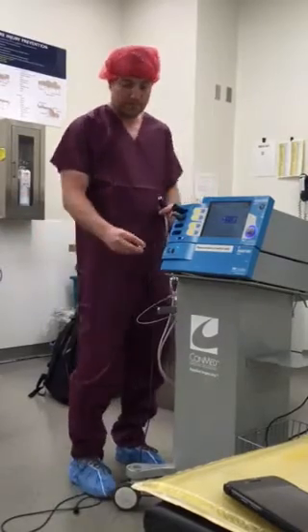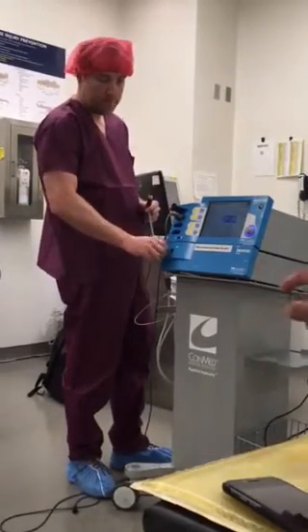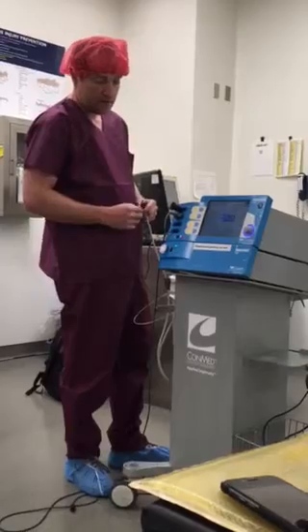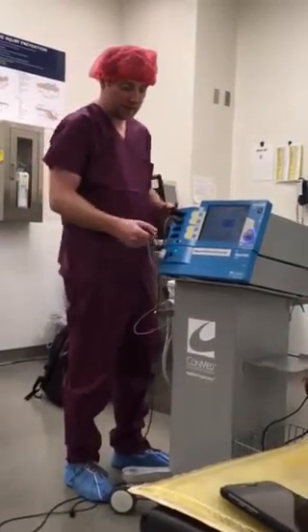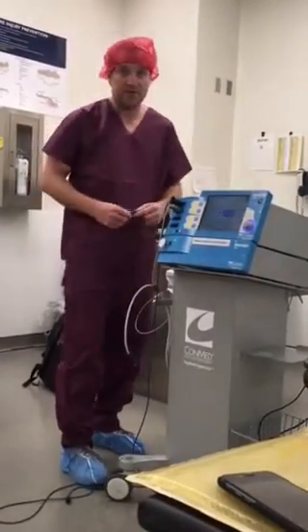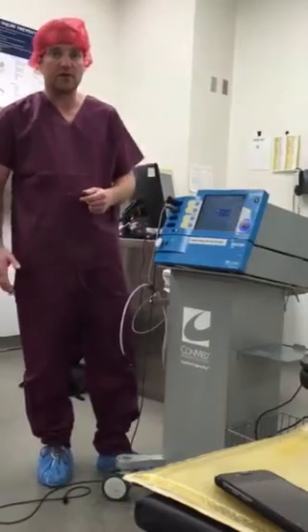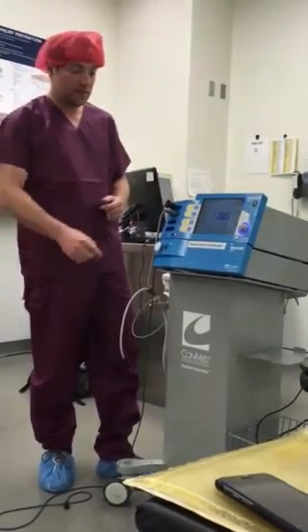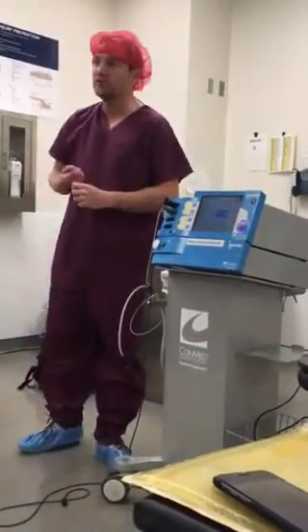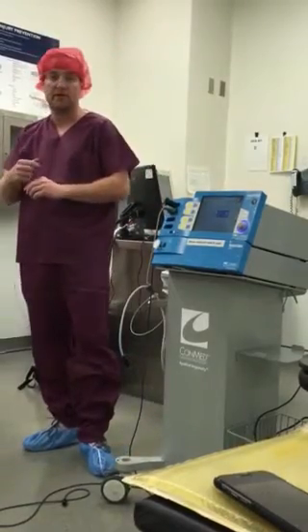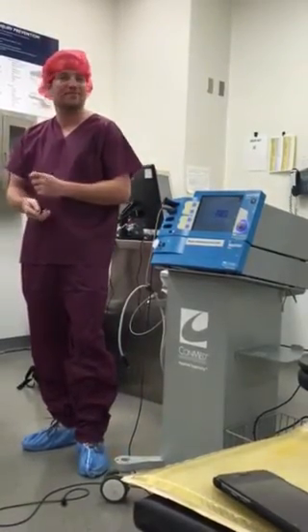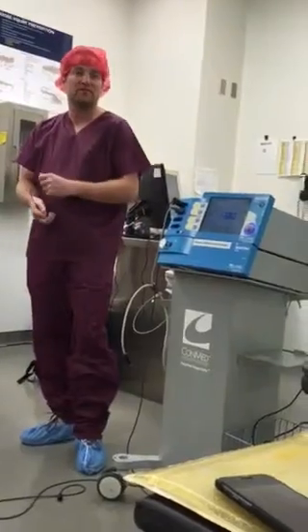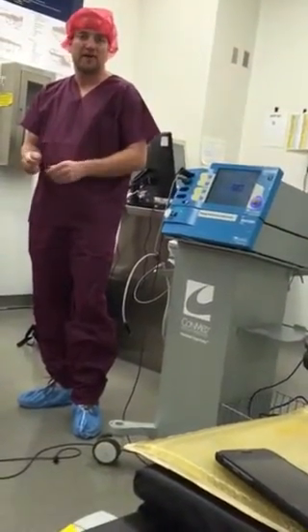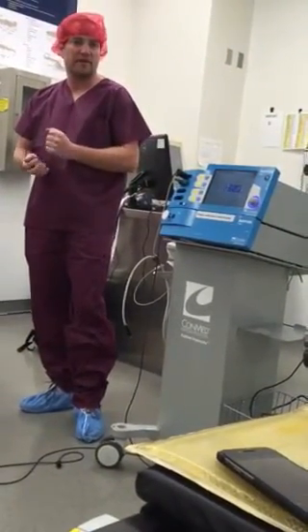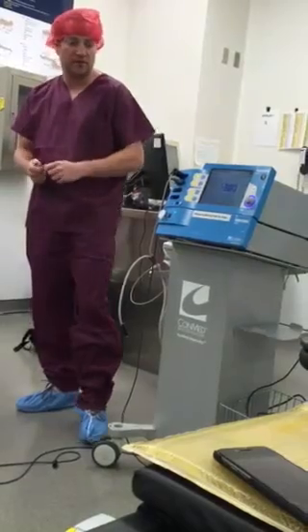Okay. I have a question. I noticed that red light indicators keep blinking. Yes, so this is a monopolar procedure, so you need a return electrode, the patient pad. You take your return electrode and plug it right in there. All argon procedures are monopolar, so you do need a return electrode. It doesn't really matter whichever pads you use, the ConMed ones or 3M or Valley Lab, whichever ones you guys use should work fine.